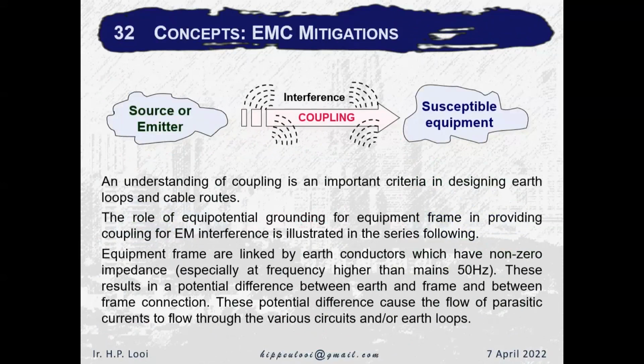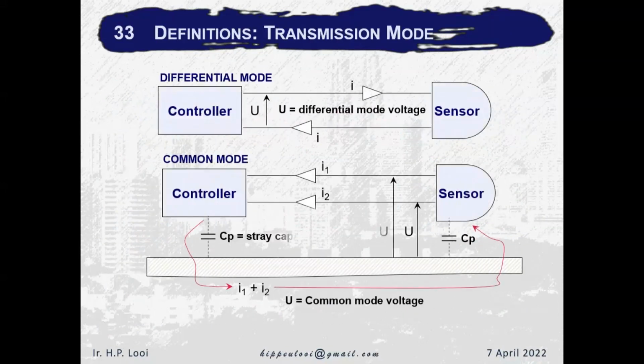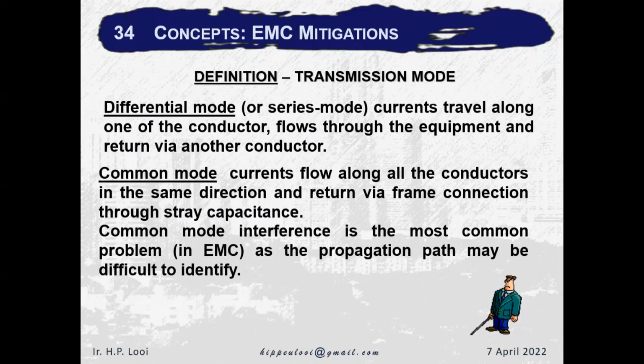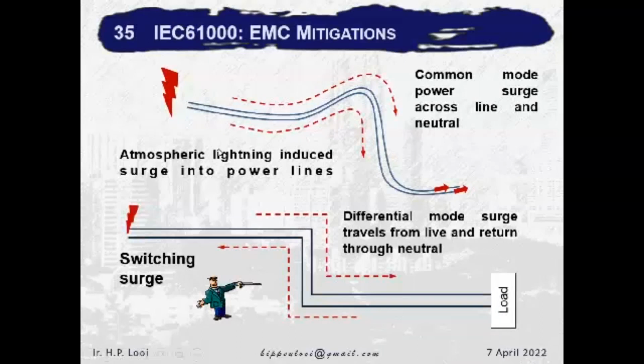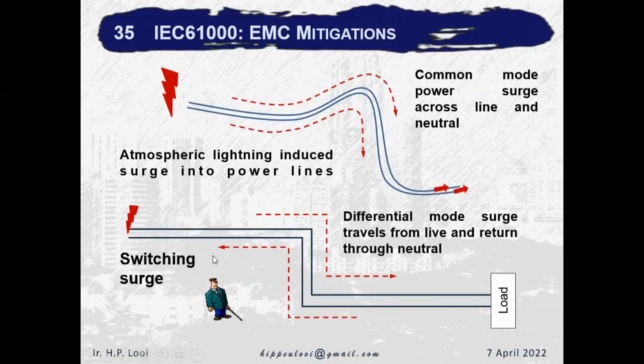What is coupling? Coupling is when a disturbance signal is transmitted from a source to an equipment. And it can be either radiated or conducted. Now, in the conducted mode, we actually have two kinds. One is called differential mode, and the other one is called common mode. This is what we call a circuit representation. Now, if we look at it, this one is clearer. Common mode is usually lightning, when a signal is discharged on phase and neutral, both in the same direction. Whereas in differential mode, a switching surge occurs on the phase and then returns through the neutral. So that's called differential mode.